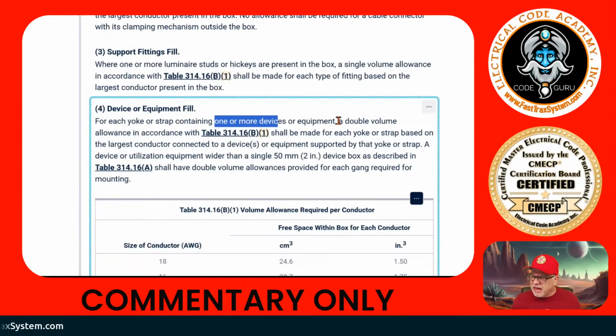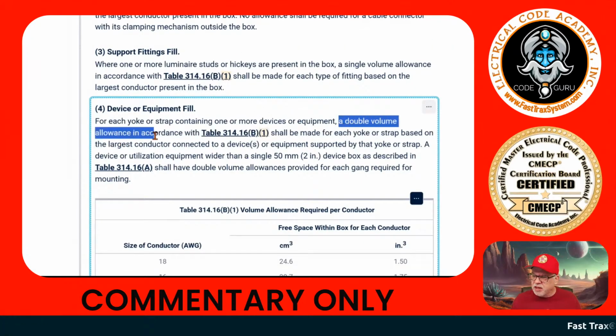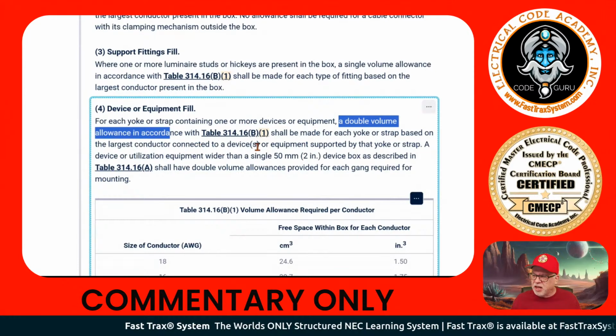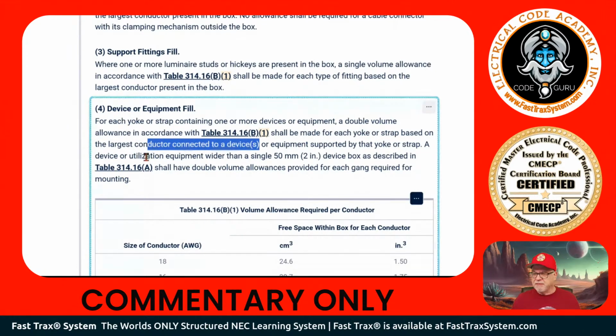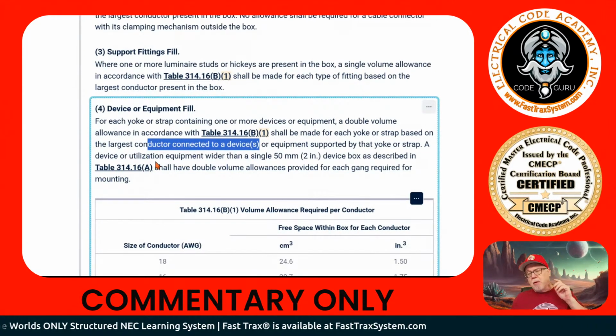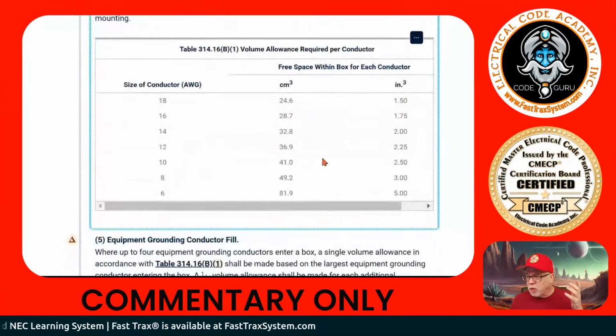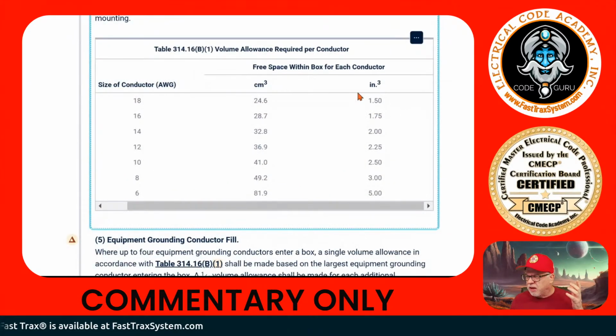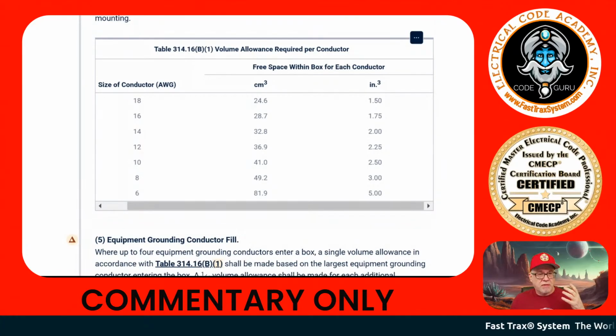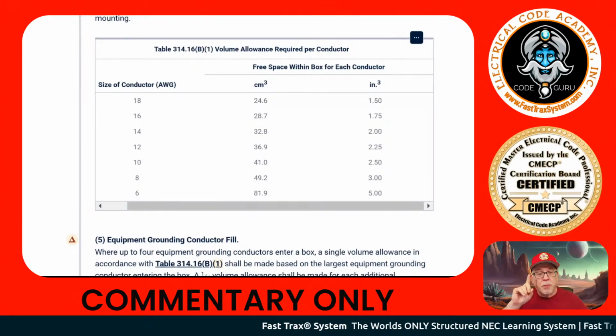It's saying a double volume count in accordance with Table 314.16(B)(1) shall be made for each yoke or strap based on the largest conductor connected to the device. Okay? Makes sense? Now, many people here will start going down here and start doing volume counts. Okay? But you have to remember the question. Okay? Just remember, let's go back to the question. Again, these are important things I want to point out.